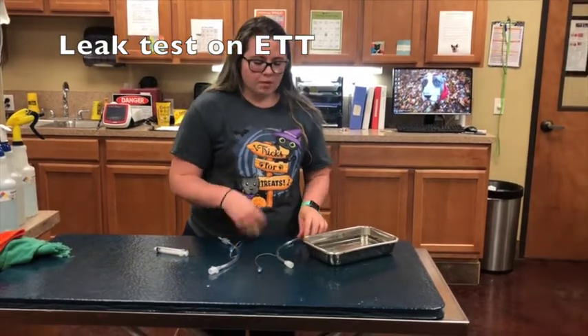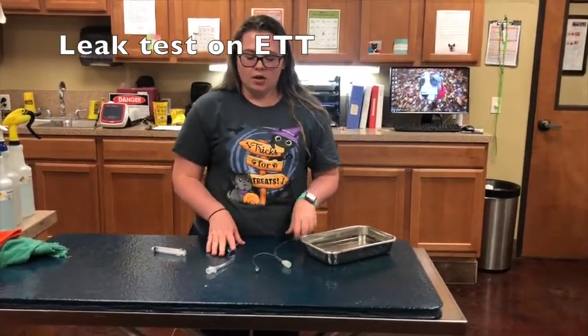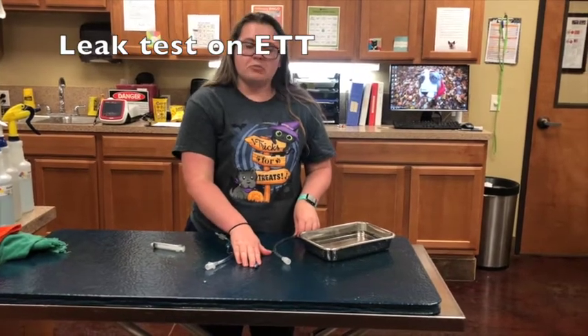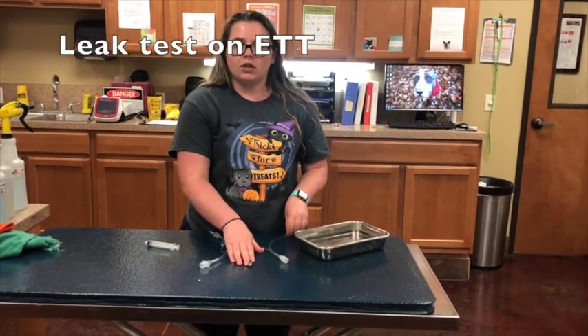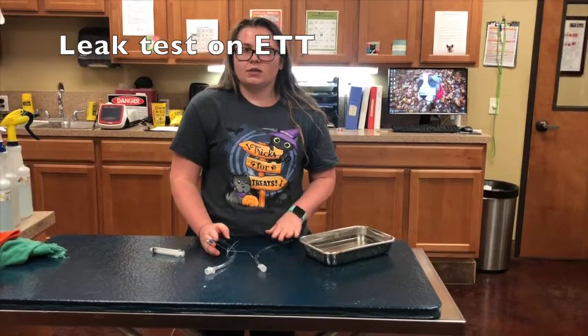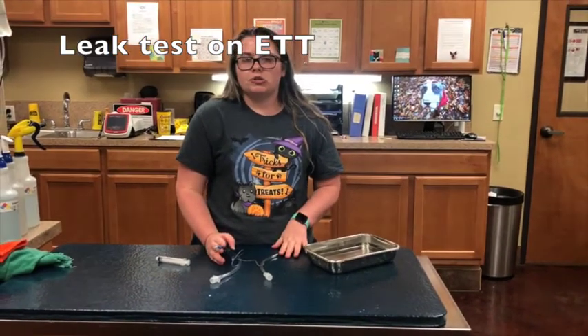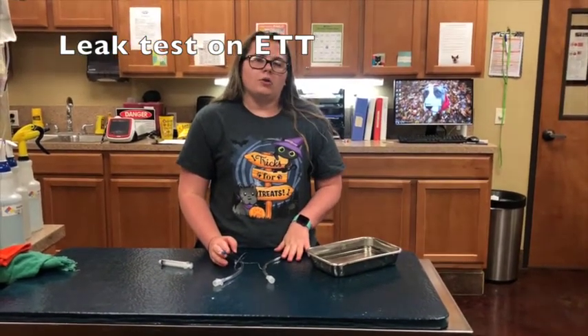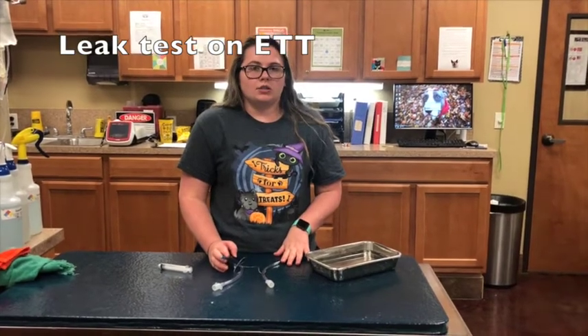Now I'm going to show you how to do a leak test on them. Leak testing makes sure there's no air leaking from the tube inflation, because if that's the case the tube will not stay in the trachea properly, and your patient may not stay asleep during anesthesia.